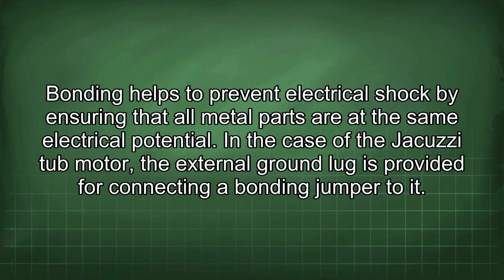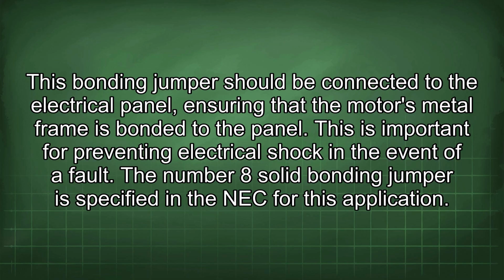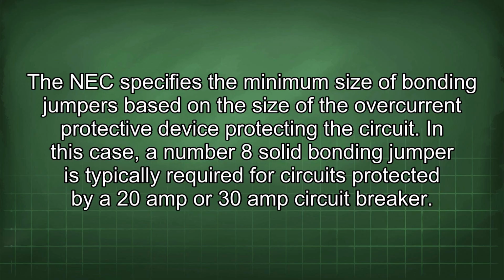In the case of the Jacuzzi tub motor, the external ground lug is provided for connecting a bonding jumper to it. This bonding jumper should be connected to the electrical panel, ensuring that the motor's metal frame is bonded to the panel. This is important for preventing electrical shock in the event of a fault. The number 8 solid bonding jumper is specified in the NEC for this application. The NEC specifies the minimum size of bonding jumpers based on the size of the overcurrent protective device protecting the circuit. In this case, a number 8 solid bonding jumper is typically required for circuits protected by a 20 amp or 30 amp circuit breaker.